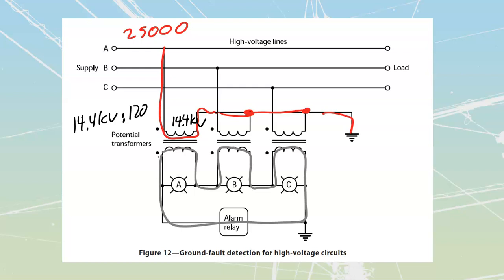Normally, this alarm relay is basically taking the place of the connection between my A and my C. It's the same as if current was coming from here to here to here. So this alarm relay is placed right across this point, which should net to 0, so there's really a net difference of 0 volts placed across there.